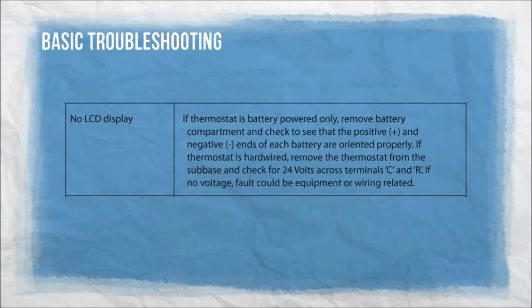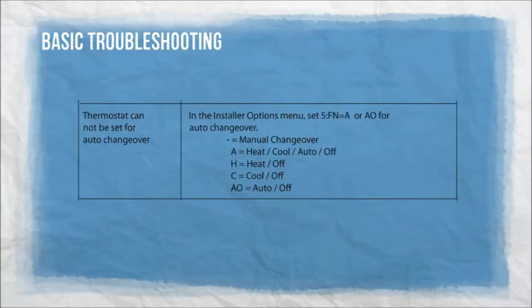Basic troubleshooting — no LCD display. If the thermostat is battery powered only, remove the battery compartment and check that the positive and negative ends of each battery are oriented properly. If the thermostat is hardwired, remove the thermostat from the sub base and check for 24 volts across terminals C and R. If no voltage, the fault could be equipment or wiring related.